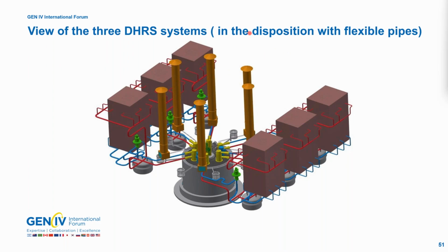The design shows flexible pipes, which is not the final layout of the reactor, but this schema shows the 6 casings of the secondary loops that are able to work by natural convection. If you open the gates, by natural convection they can ensure the DHR. We have the 6 chimneys of the DHRS1 systems that are related to the heat exchanger, and the DHRS3 are inside the primary vessel or around the main vessel. And with the 3 systems, we are able to have a very efficient evacuation of the decay heat removal.